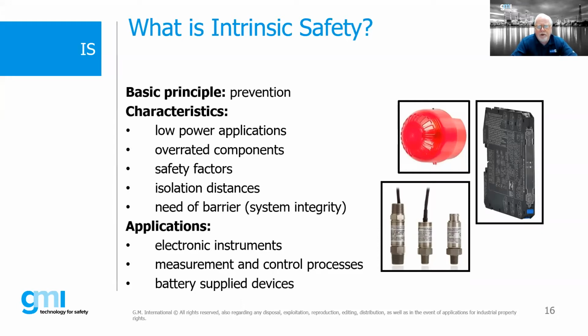So the applications, again, electronic instruments, measurement and control processes, battery supply devices. So anywhere where you're basically looking at low voltage, 12, 24 volt DC type circuits, in many cases, that's a very good application potentially for use of intrinsic safety. Now, there are alternatives to going intrinsic safety, and some people don't use intrinsic safety. You will find, for example, transmitters that are rated Ex d, that are flame-proof. But you'll see a transmitter that can be done either Ex d or Ex i, and you have to wire it up accordingly and design it accordingly to the protection concept used. Now, some people will say, hey, I want to use a 4 to 20 milliamp Emerson Rosemount transmitter. You can certainly do it and do it as flame-proof, for example, but you have to make sure that the glanding, the cabling, and everything else is suitable for that application.